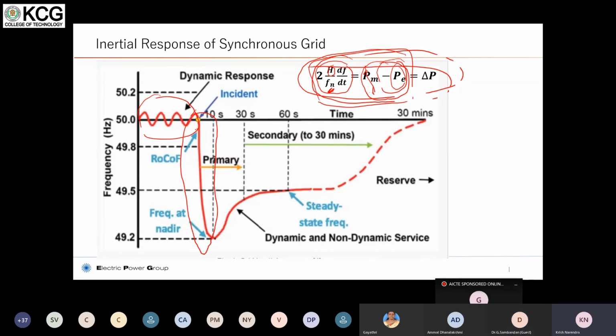So the moment higher renewable penetration is there, techniques such as virtual inertia and other concepts come into the picture. Now, if I elaborate that question and ask what will happen if there is 100% renewable, then you don't have to worry about inertial problems, right? A grid can be operated with no inertial support. Why not? If you do not have any inertial problem in a system, then the frequency response becomes very fast. Under such circumstances, the philosophy of protection and other things that we are doing today needs to be adapted to the newer situation. But it is always possible to control these things and mitigate them.